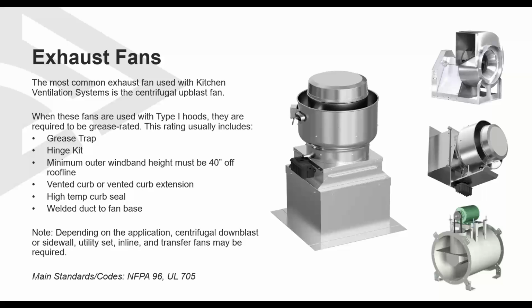Looking at exhaust fans, the most common exhaust fan that we see used in a kitchen ventilation system is our centrifugal upblast fan. When these fans are used with a Type 1 hood, which is our grease-rated hood, they're required to be grease-rated as well. This rating usually includes a grease trap, hinge kit, an outer wind band height of 40 inches off the roof line, vented curb or vented curb extension, high temp curb seal, and a welded duct to the fan base. Depending on the application, you may also see centrifugal downblast or sidewall fans, utility set, inline, and transfer fans. Just depends on the application. And the main standards that we follow are NFPA 96 and UL 705.